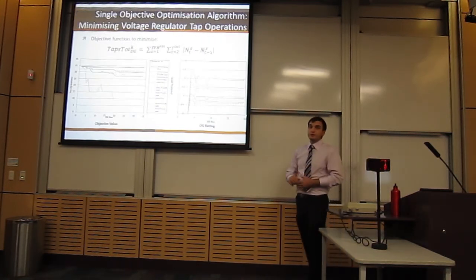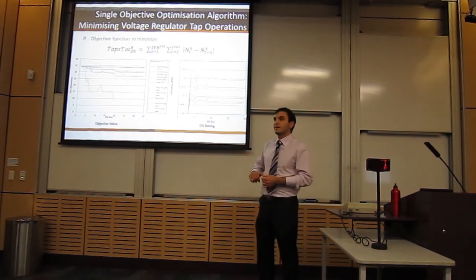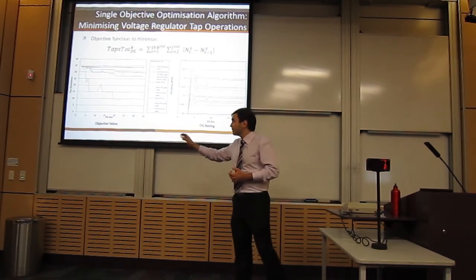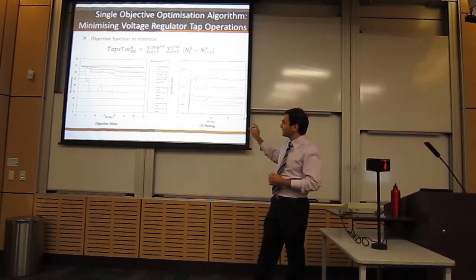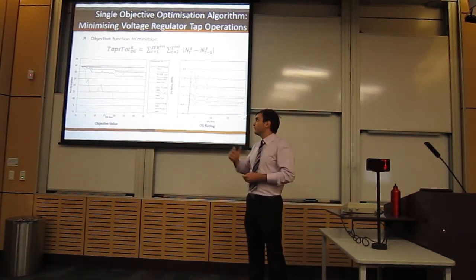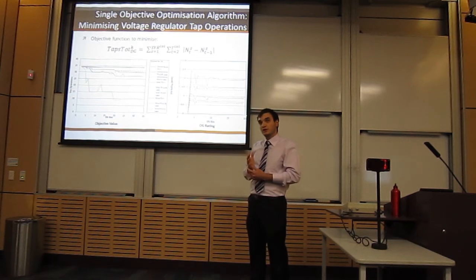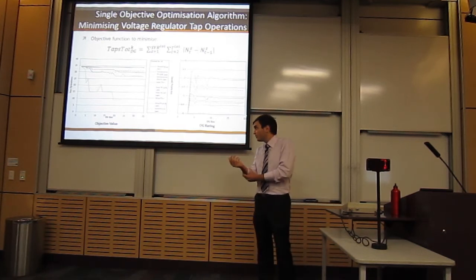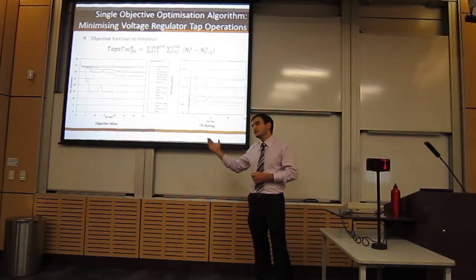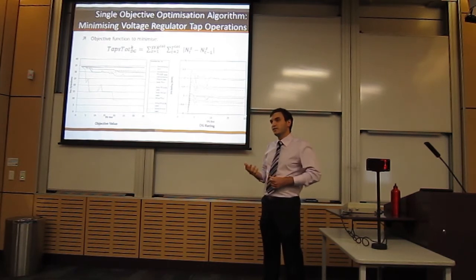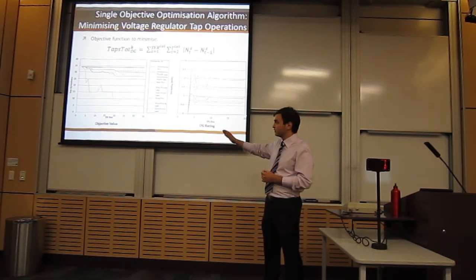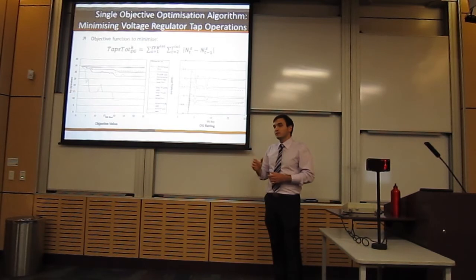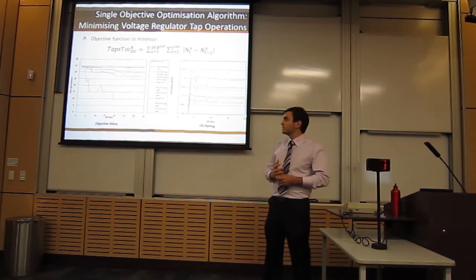The first optimization algorithm implemented was that to minimize voltage regulator tap operations. For the graphs presented, the x-axis shows the bus at which the DG was implemented, with bus 1 being the grid connection and bus 34 being the most remote bus. The y-axis on the left graph shows the objective value, and the y-axis on the right graph shows the corresponding DG rating. It can be seen that by implementing DG towards the end of the feeder, the most significant reduction in tap operations can be achieved.